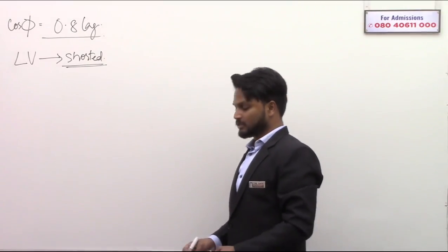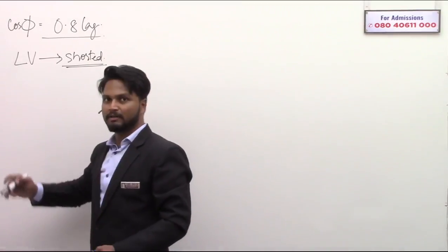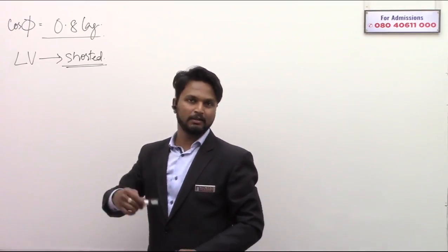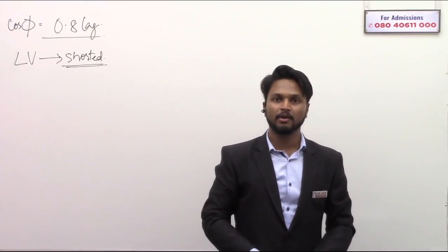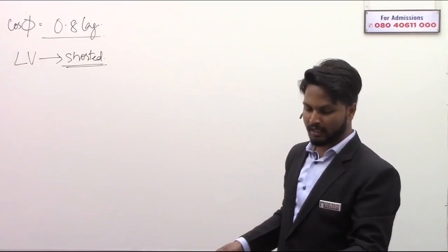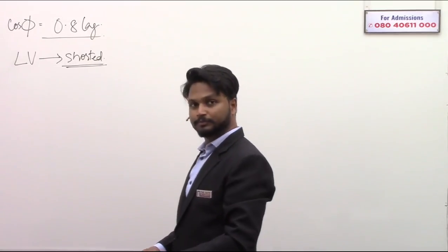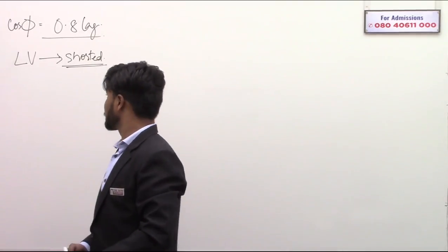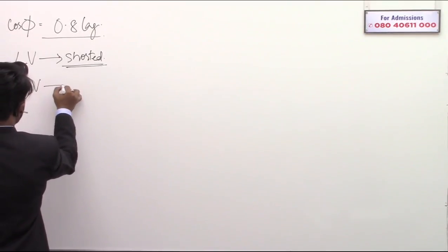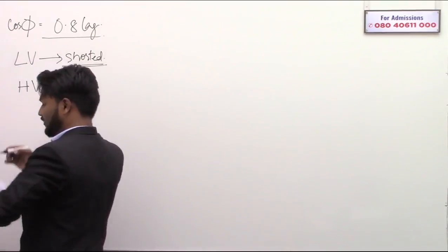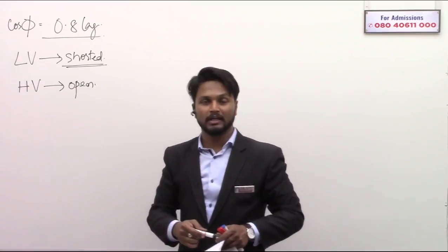So tell me, someone please explain why we have to short only the LV, the low voltage side, while performing the short circuit test, and not HV. And while performing the open circuit test, only HV is open circuited. Why not LV? Only HV is open circuited, why not LV?